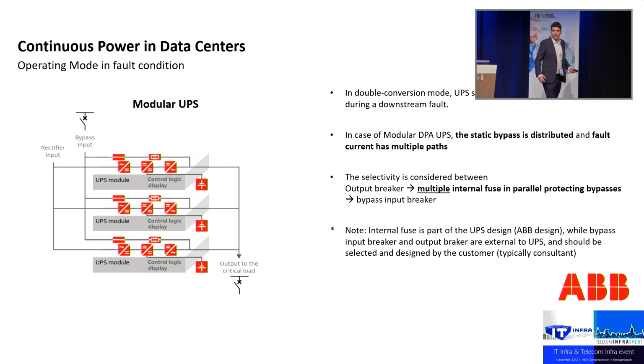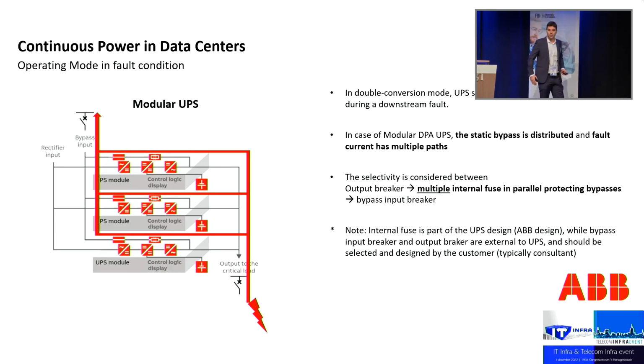Let's analyze more complex systems. So in case of modular UPSs, the true modular UPS each module has a static bypass inside. So it means that I also have, for each static bypass, a fuse which is protecting this bypass. So it means that I actually have 3 fuses in parallel. So in case that I have a fault, I do not have anymore just one current flowing through the UPS. I actually have a current which flows through each static bypass and thus through each fuse inside of the bypass.